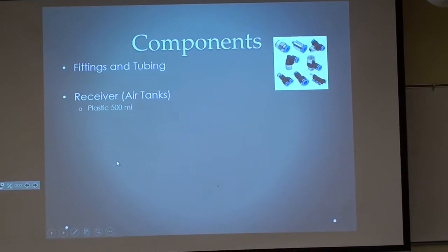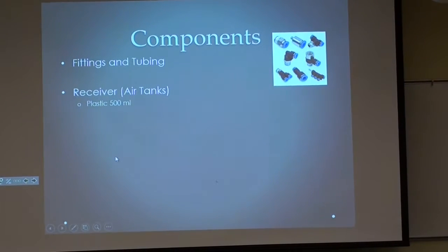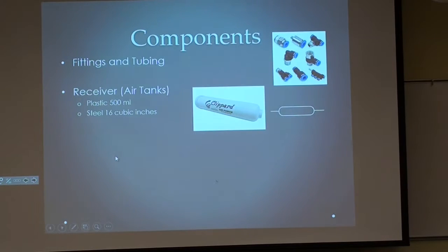Okay, receiver tanks, that's what this is. Anybody want to comment about that tank right there? Come on, Ted, you know the answer? You chuckled. Yeah, I do. That tank is illegal. You cannot use the Clippard white tanks, because they have a tendency to explode. The Clippard black tanks are legal, Clippard white tanks are not.